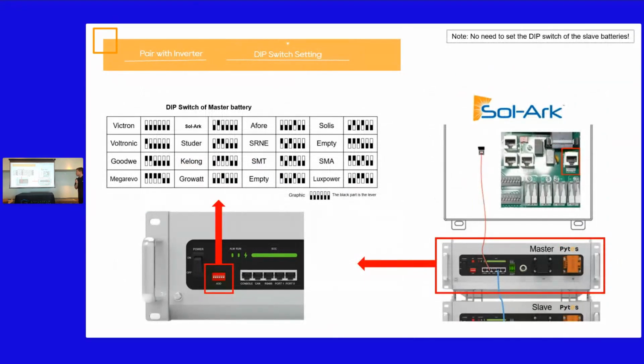After finishing the wiring, we need to pair our battery with the inverter. First, select the correct communication protocol according to your inverter brand by adjusting the dip switch on the master battery. For example, if we want to communicate with the Sol-Ark inverter, we choose pin 2 on.